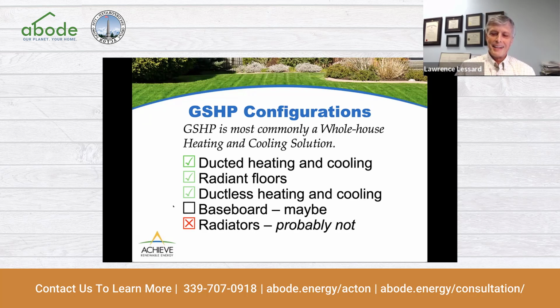Baseboards are possible, but really not commonly done. Ground source heat pumps can't make the same temperatures that a boiler will. If you have baseboards, your boiler probably circulates 160 to maybe 175 degree fluid through the baseboards. Ground source heat pumps top out at about 150 for the maximum, and that's only a couple of pieces of equipment can do that, and other ones are limited to lower temperatures. So the output of the baseboard is reduced.